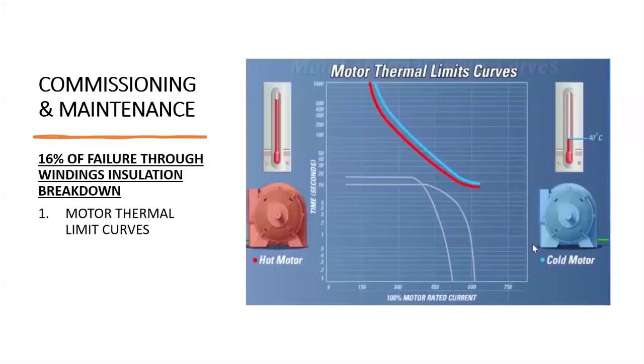Now let's look at typical examples of motor thermal curves. The red curve shows the motor thermal curve when the motor is hot. What do I mean by motor hot? A motor is hot when it is running and in operation. That motor is called hot. And a cold motor is a motor which has stopped, and the cooling time for it to cool to the ambient temperature has elapsed. Maybe the cooling time is 20 minutes. If the motor has stopped and the cooling time of 20 minutes has elapsed, that's a cold motor.